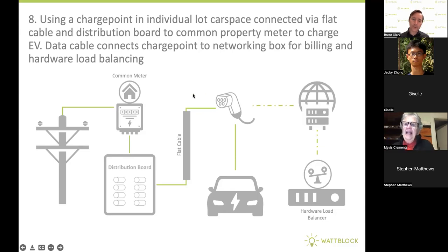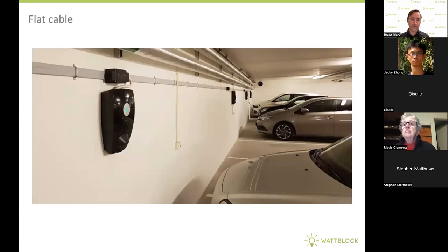The key difference in this model is we're using a flat cable instead of a cable tray with individual cable lines for each charge point - one flat cable will have multiple charge points connected to it. This scenario probably looks better after seeing a picture of the flat cable - a picture tells a thousand words. Here is a flat cable, also called a bus duct, bar, or busway, running along the perimeter of the basement car park.